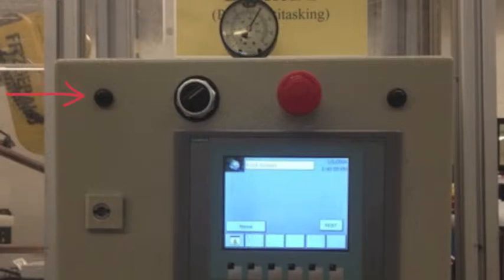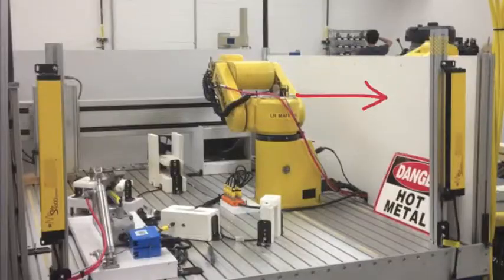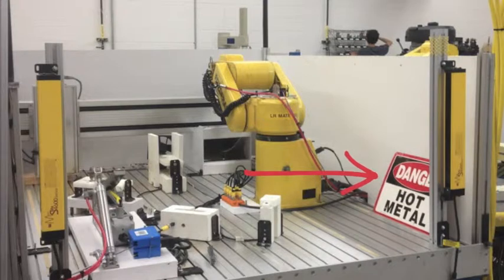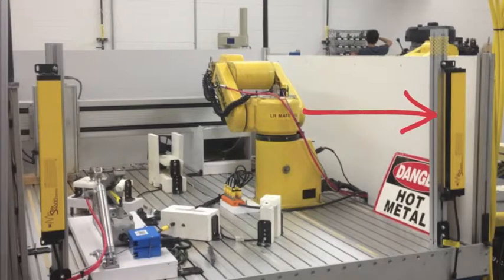The double operator start requires the personnel to press each button simultaneously. This signals the FANUC UOP start, which enables the robot and runs the program. Physical barriers are used to prevent personnel from entering the work envelope. The signs are used to make aware of the possible hazards that are within the work envelope itself. Just like the E-stop, the light curtain is normally closed and will also fault the FANUC hold when broken.